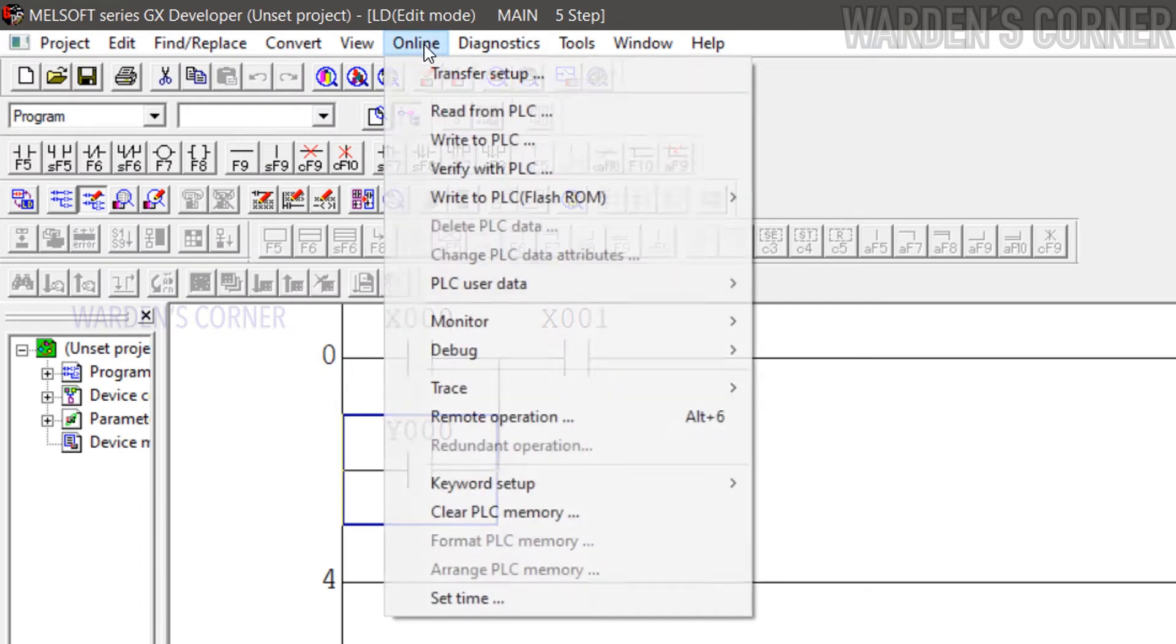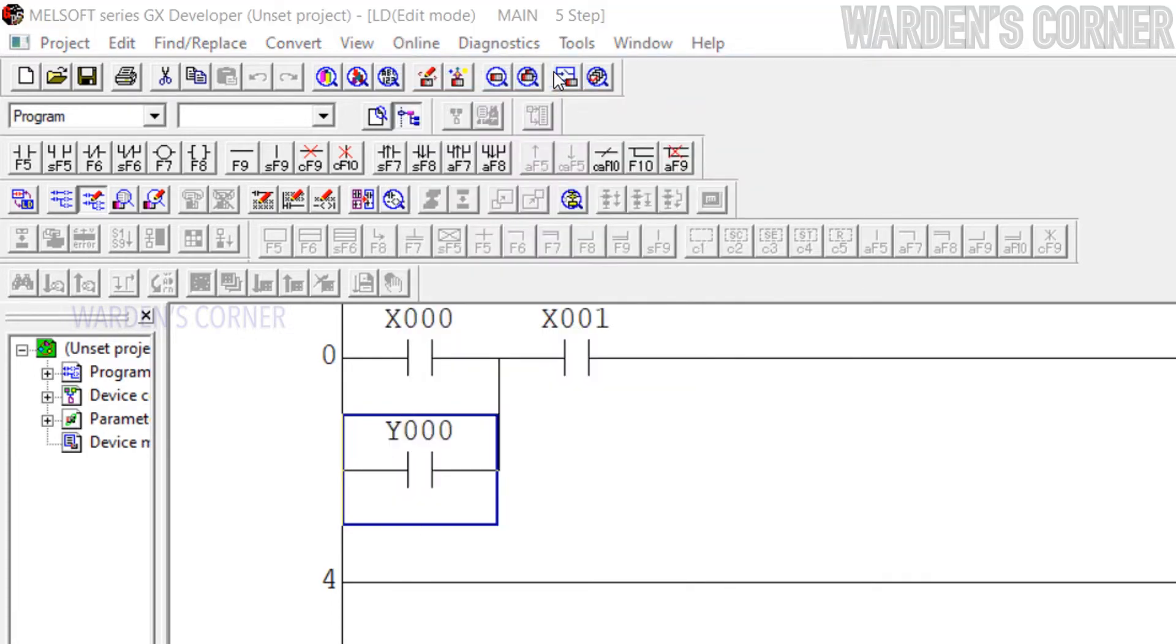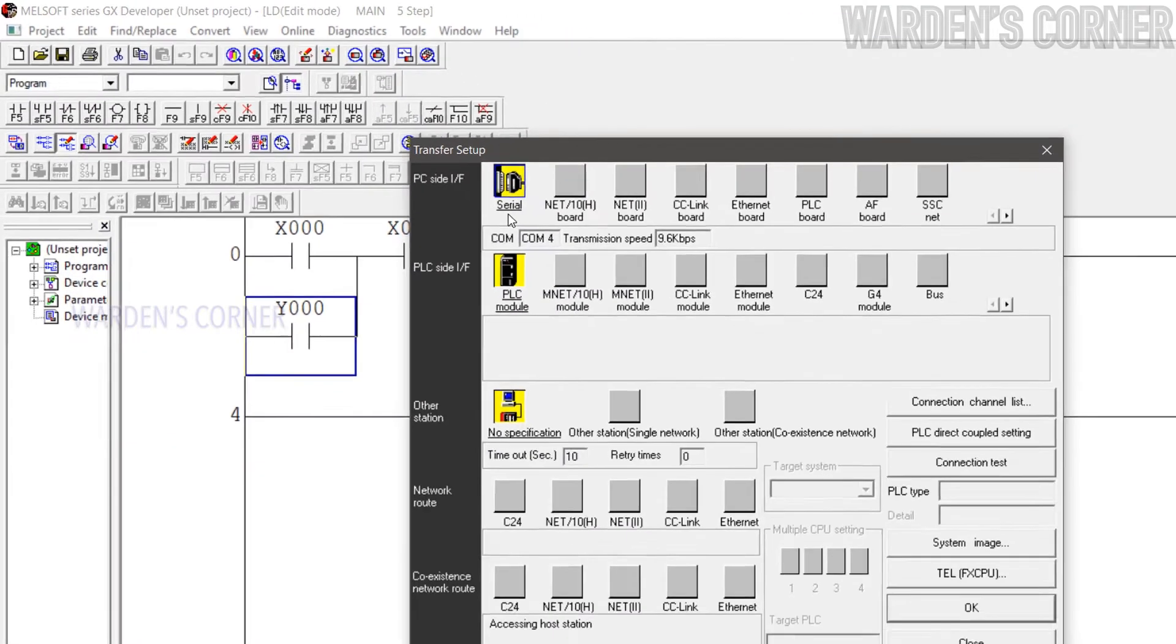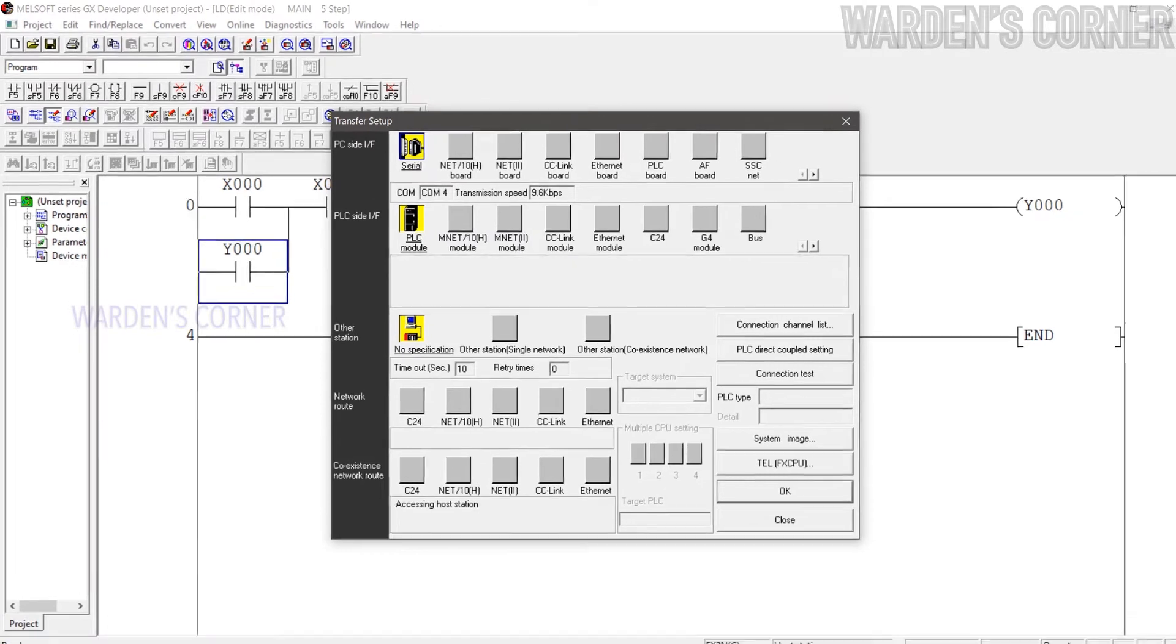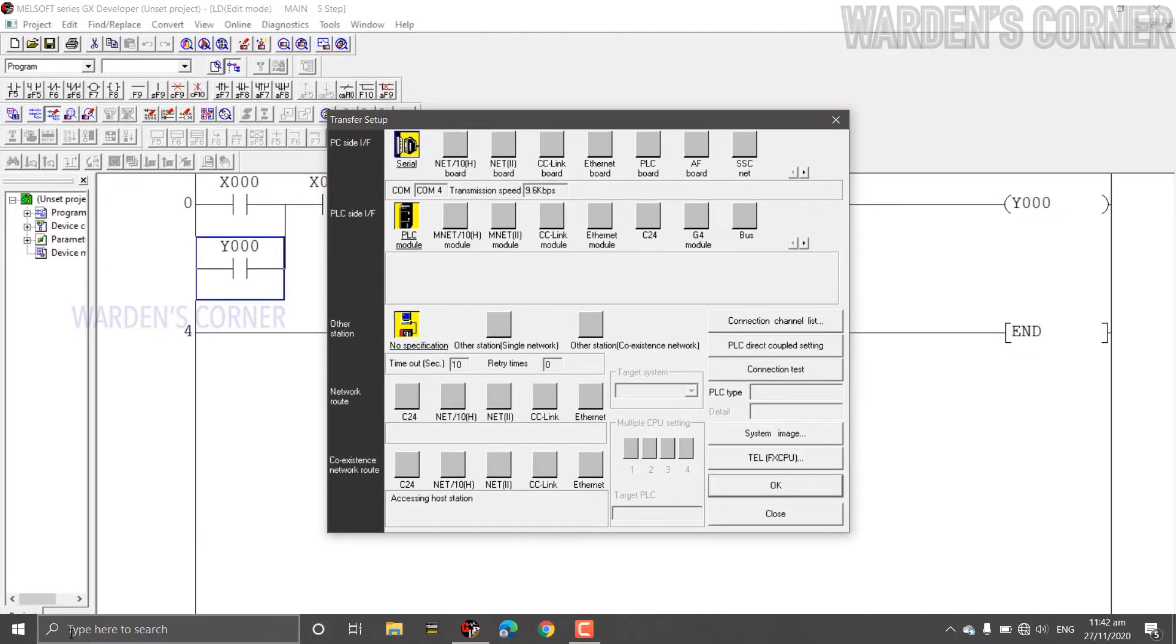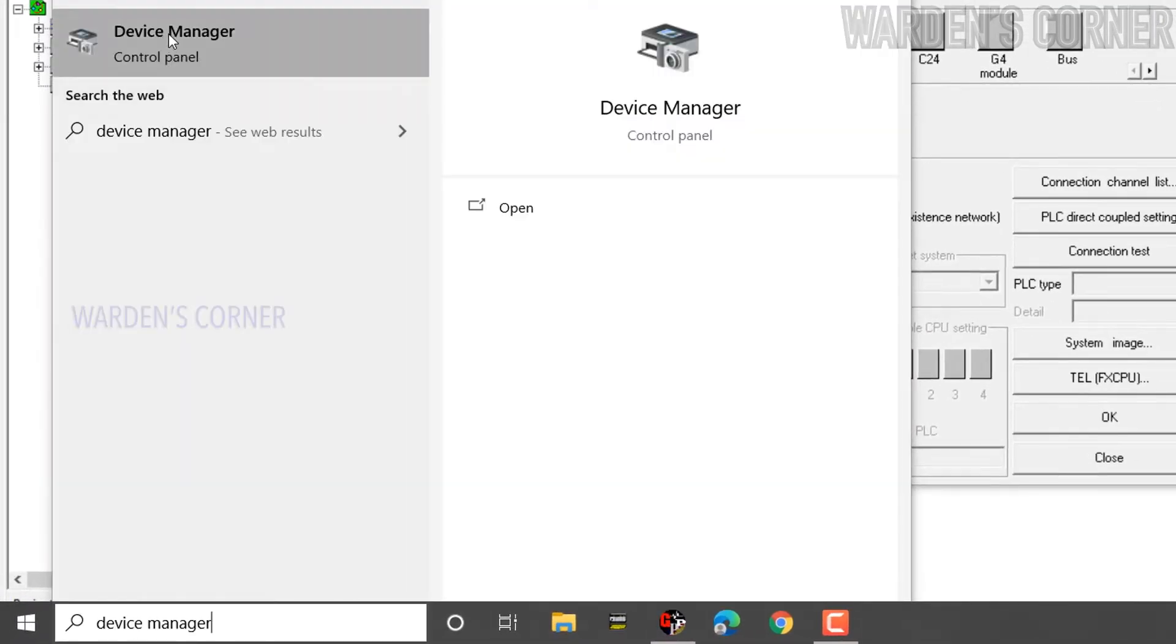At Menu, select Online, click Transfer Setup. A new tab display will appear. It is where you can set up the laptop to PLC communication by properly selecting the COM port number. COM port connection can be accessed at Device Manager tab. Go to Search, type Device Manager and click.